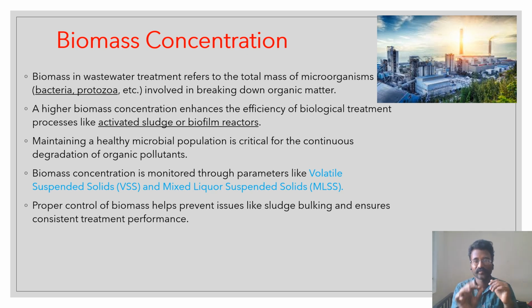Biomass concentration is monitored using parameters like volatile suspended solids, VSS, and mixed liquor suspended solids, MLSS. Proper control of biomass helps to prevent issues like sludge bulking, and also helps in consistent treatment performance.